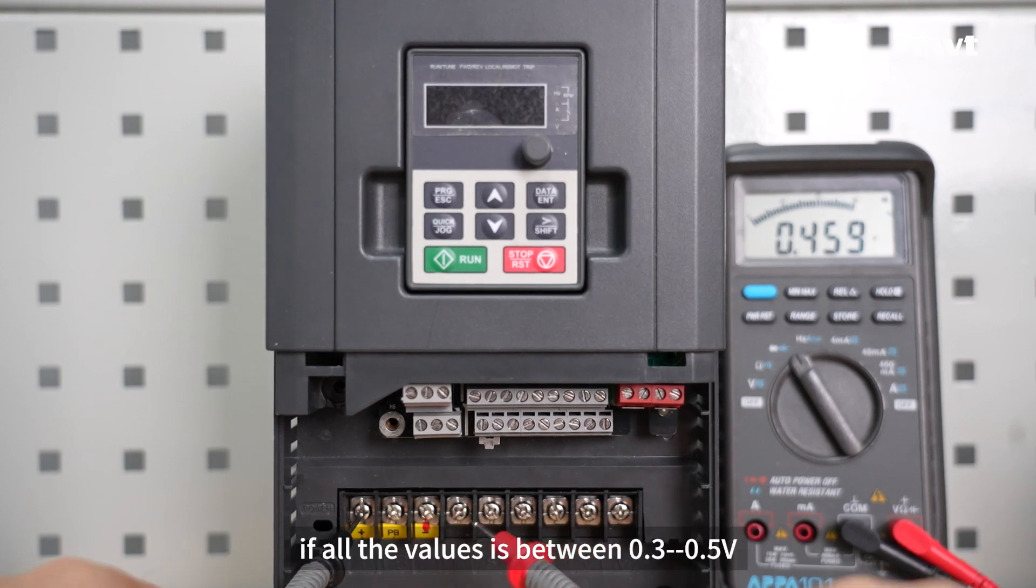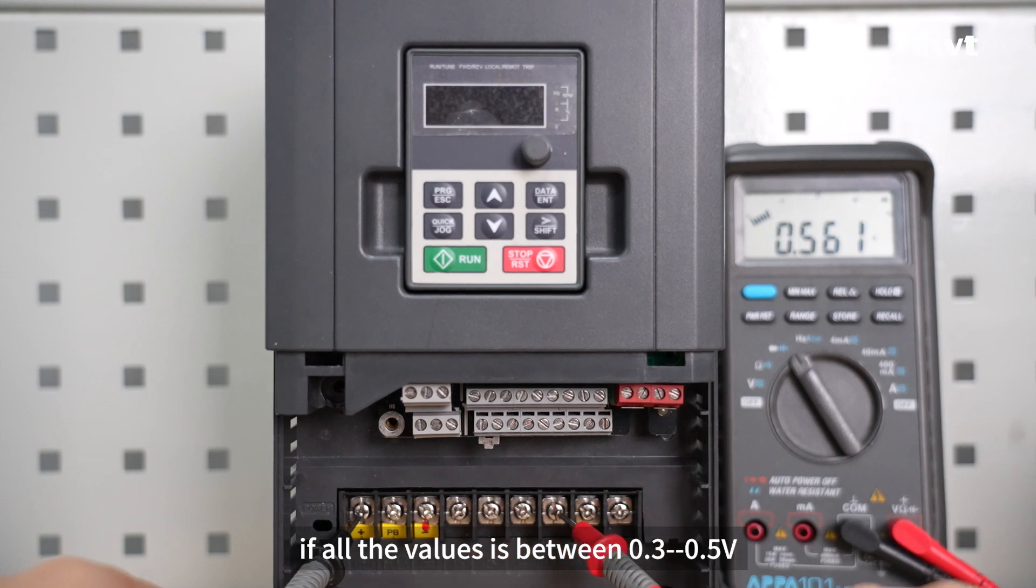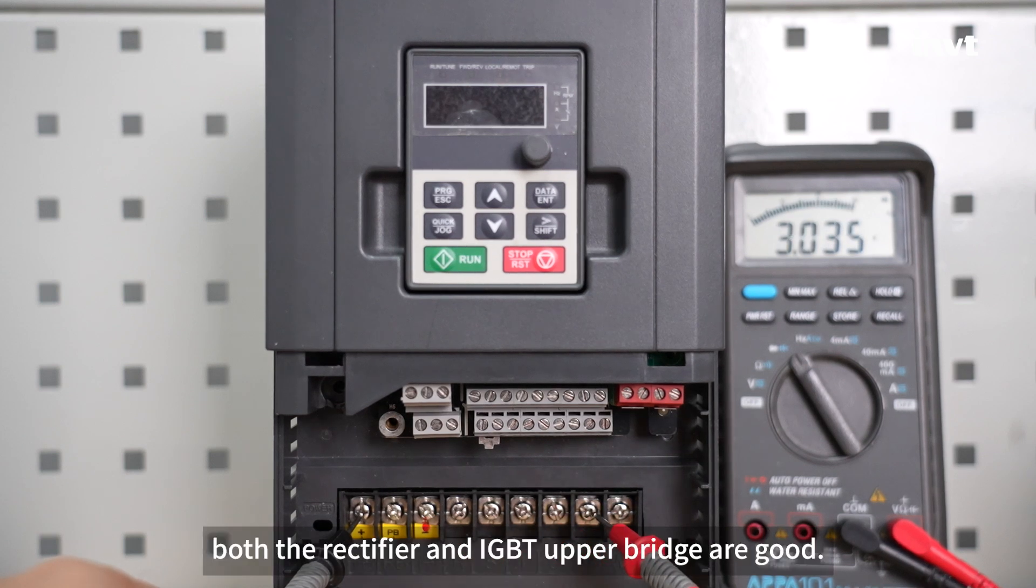If all the values are between 0.3 to 0.5 volts, both the rectifier and IGBT upper bridge are good.